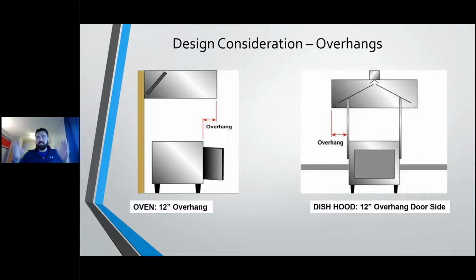Same goes for dish hoods, where these doors close, and then when they open, a bunch of condensate can run out. The reason being is that when you open these doors, so let's say you had baked potatoes in your oven for the last 45 minutes at 450 degrees. When you open that door, the velocity of that door opening takes the air out of the oven with all that hot air, and that velocity has the potential to exceed that 6-inch overhang. So if you give it a 12-inch overhang at the front, it gives the hood more capture tank in order to overcome that velocity moving out.